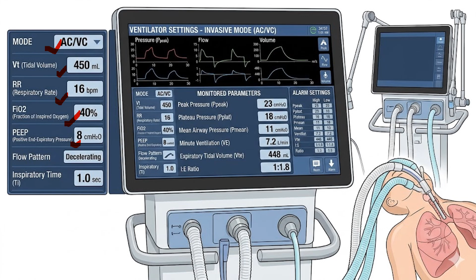Now, moving on to RR or the respiratory rate, this is the number of breaths per minute. The normal setting is from 12 to 20 breaths per minute. Then we have the FiO2 or the fraction of inspired oxygen, the percentage of oxygen delivered. So it ranges from 21% room air to 100%. Then we have the PEEP or the positive end-expiratory pressure. This is the pressure left in the lungs after exhalation. This prevents lung collapse, and typically it starts from 5 centimeters of water. Now, we have to remember that the tidal volume and the respiratory rate represent the ventilation, and the FiO2 and the PEEP represent oxygenation.